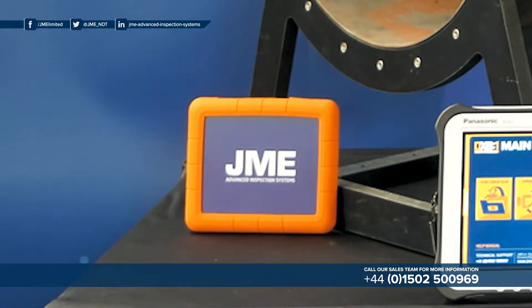In addition to the DXB unit itself, the system is also supplied with a control tablet. This is a fully fledged Windows 10 based PC. It has all of the standard connectivity associated with a PC, including HDMI out, USB connections, as well as WiFi in order to remove images from it and potentially transmit them to a remote location. The system is also supplied with a RAID configured hard drive, which is a requirement of some standards in terms of image backup.